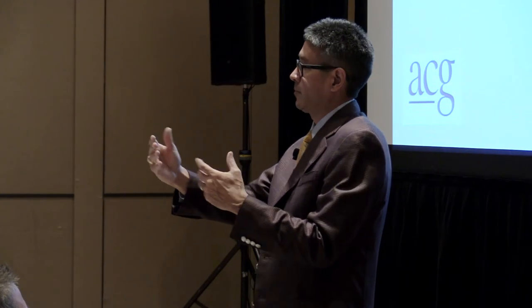To a point, Don, you're correct. That's the hard part: how are you going to do it? If you close the floor off, you've just set up a system in a one-time scenario that is not going to ever be repeated. When is that first floor never going to have water, and then you balance second and third? So what's worse? It's the old necessary evil conversation, and that's where you've got to sit down with the design professional, go through it even with the owner and say, here's what we're looking at for your building. Ask the design professional, how would you anticipate this building operating at a block load? And where can we look and say, what can we close off and how do you want to do it? The new standards have one sentence in there that makes it vague, but not vague to the point that you interpret it as we need to close off.